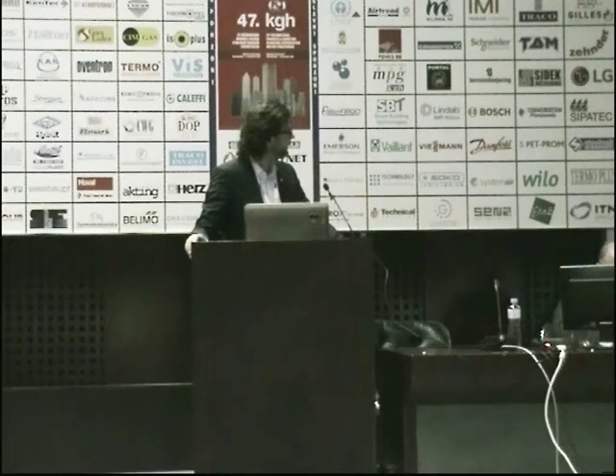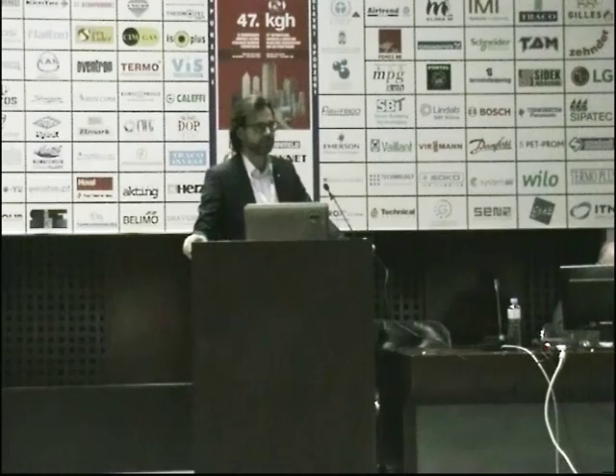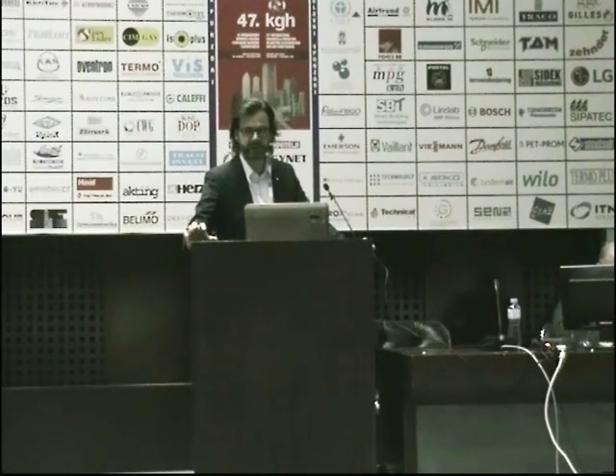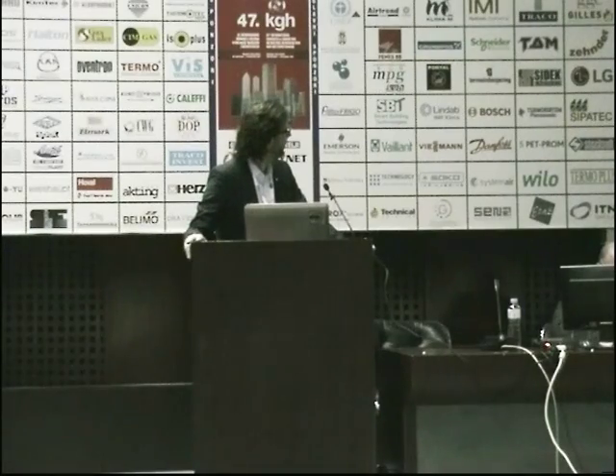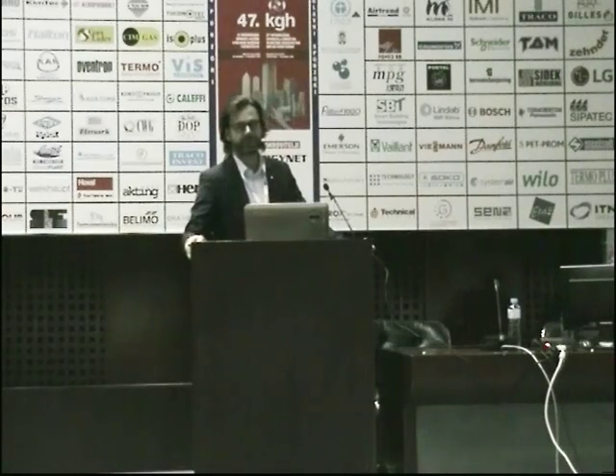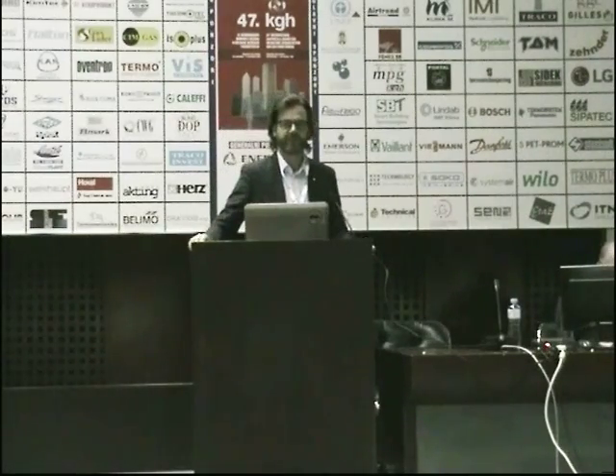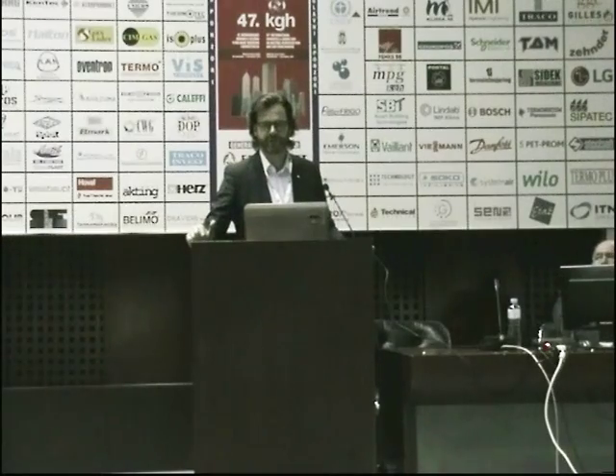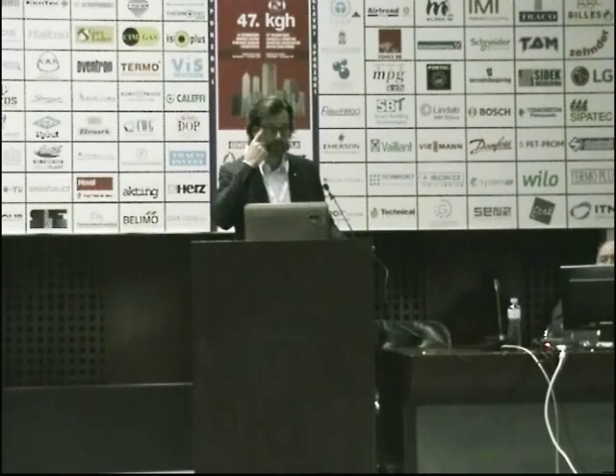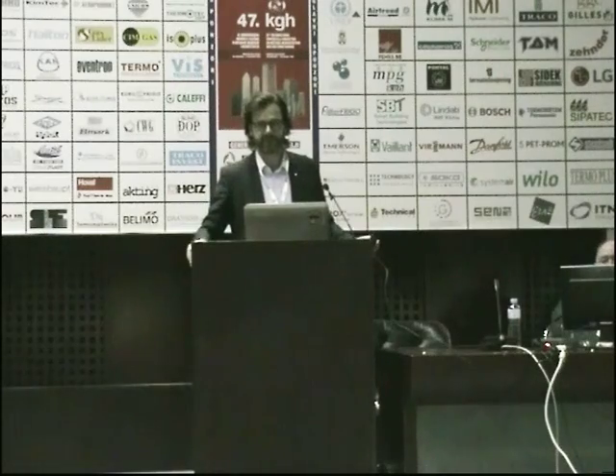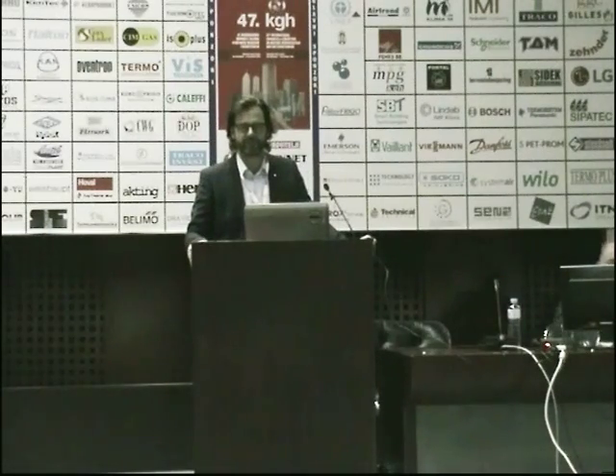The next point was we set up the system according to the EN 378 standard and according to the South African regulation and standards. The systems were checked by TÜV Germany according to EN 378. We did, for the first time in South Africa, a full documentation of the project, risk analysis, that all schematics were on site, that the schematic was on the wall in the machine room, etc., etc. I think you know all that very well.